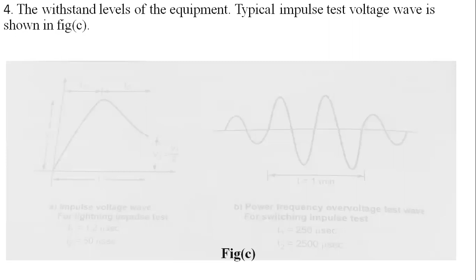The withstandable levels of the equipment's typical impulse test voltage wave is shown in this figure. This is the impulse voltage wave for the lightning impulse test. Here is our linear function, it is linearly increasing and thereafter it gets decreased, where the voltage at V2 will be half of the input voltage V1.